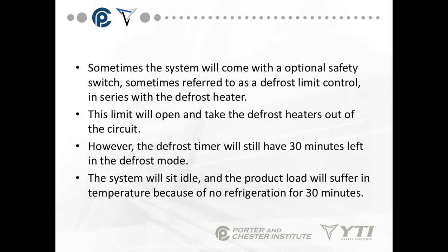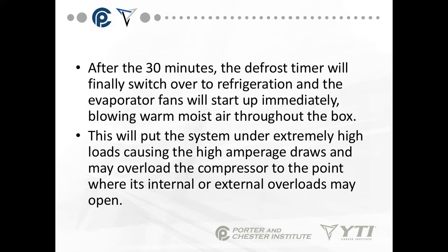Sometimes the system will come with an optional safety switch, sometimes referred to as a defrost limit control, in series with the defrost heater. The limit will open and take the defrost heaters out of the circuit. However, the defrost timer will still have the full 30 minutes left in defrost mode. The system will sit idle and the product load will suffer in temperature because of no refrigeration for 30 minutes. After those 30 minutes, the defrost timer will finally switch over to refrigeration and the evaporator fans will start up immediately, blowing warm, moist air through the box — pulling the system under extremely high loads and causing high amperage draws that may overload the compressor to the point where its internal and external overloads may open.